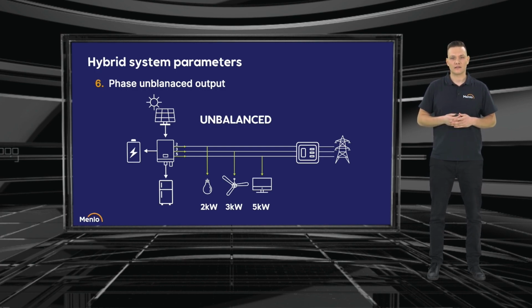The unbalanced inverter can produce the exact amount of power on each phase, depending on your needs. In this case, it produces 2, 3, and 5 kilowatts on each phase. Of course, you still need to remember the maximum output power on one single phase. So if it's 5 kilowatts, then it can work like that.